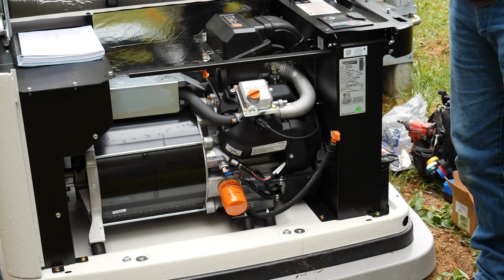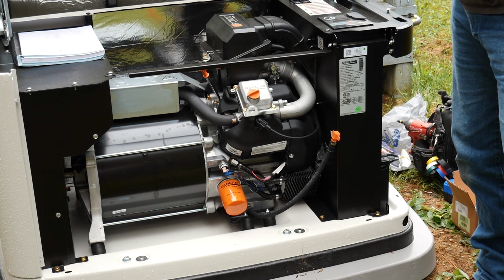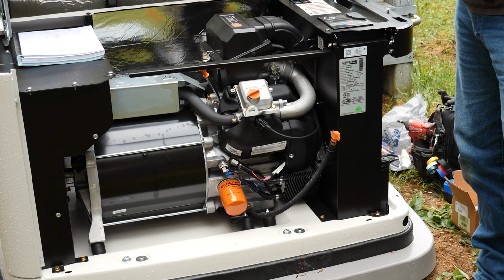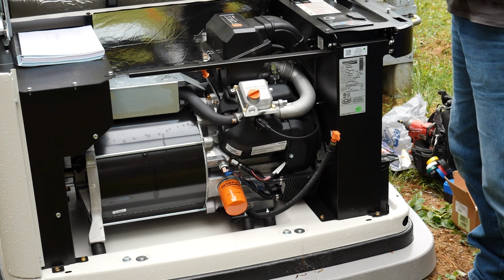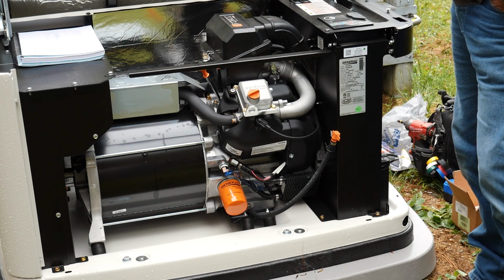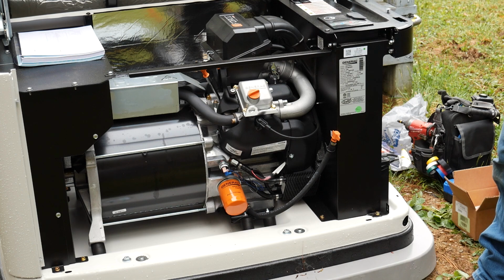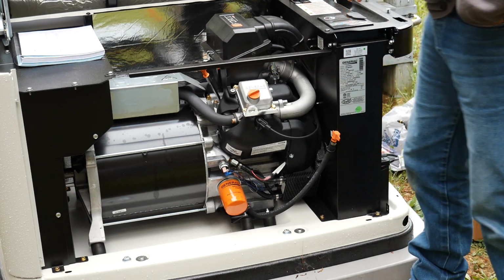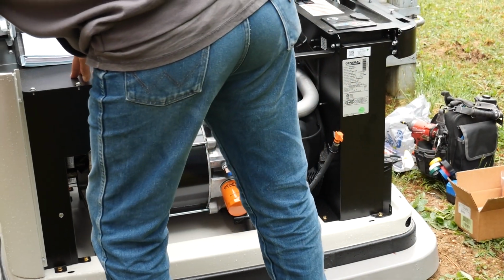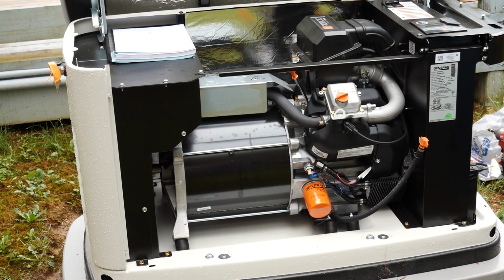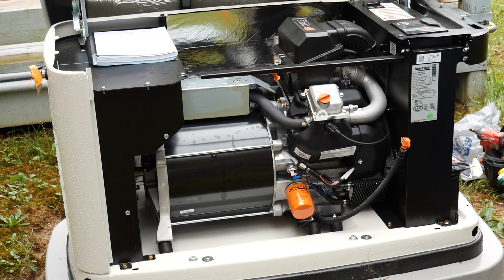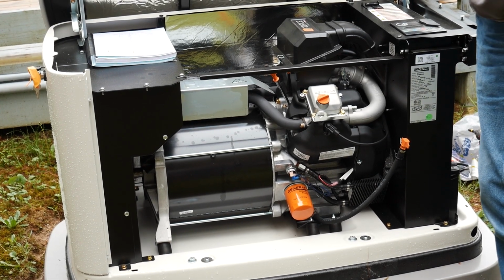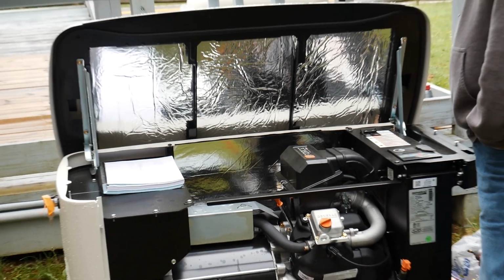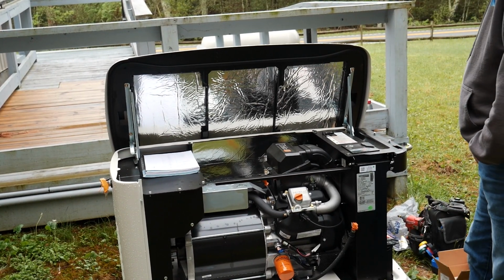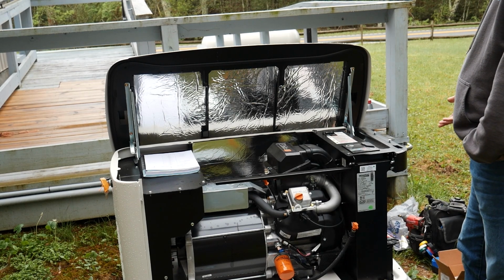What we're selling customers is an annual maintenance plan—one visit per year. It includes wiping down the exterior of the unit with a detergent cleaner, something like 409 or Simple Green in a spray bottle, then wiping out the inside. We make sure the louvers aren't blocked, check for oil leaks at the bottom of the unit, and use spray bubbles to check the gas connections in the back all the way up to the unit for leaks.